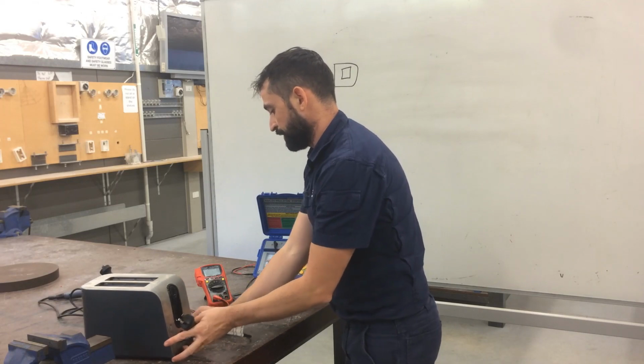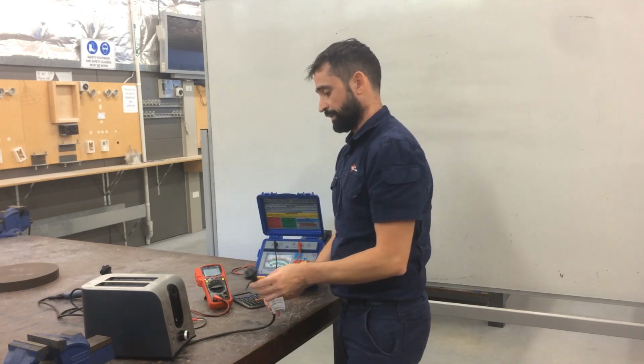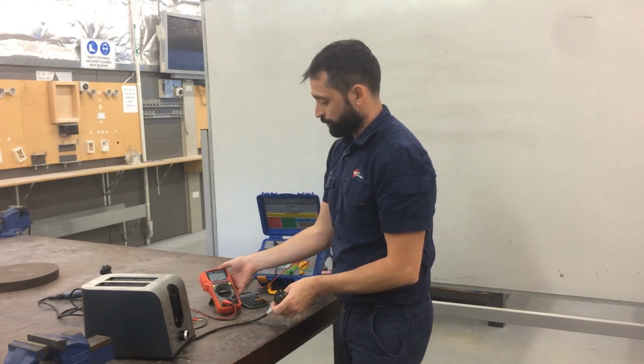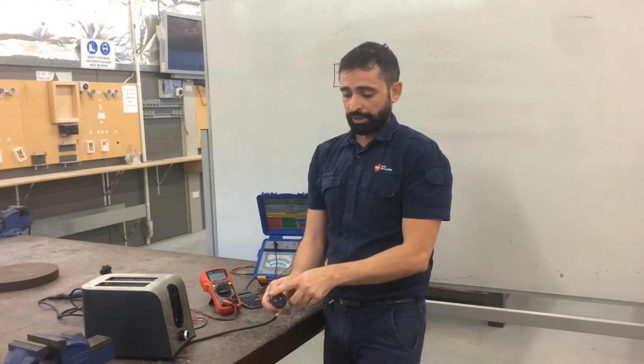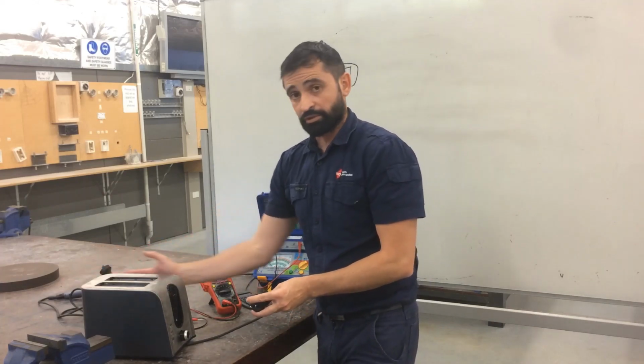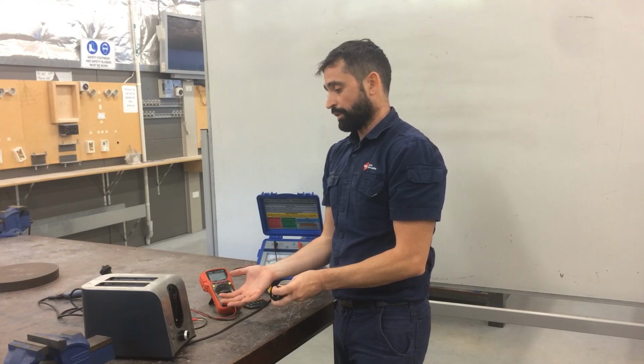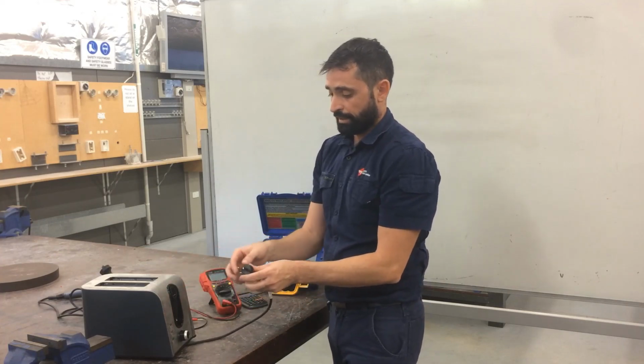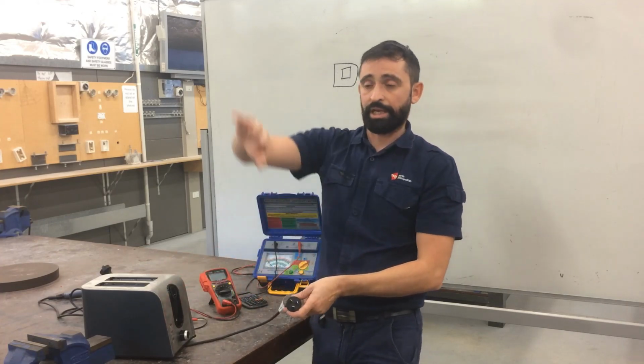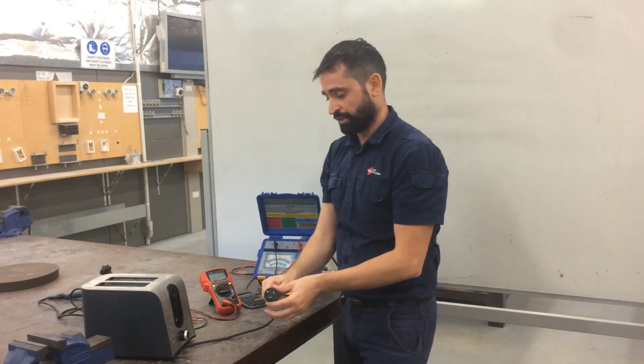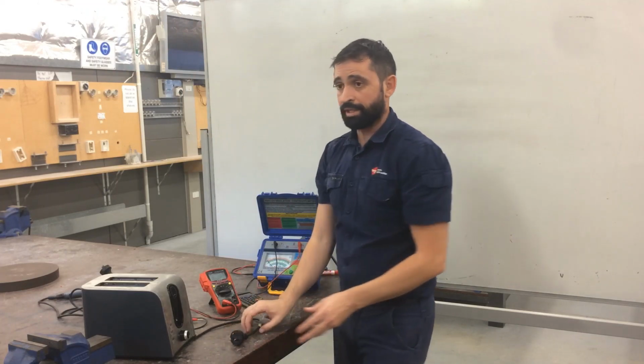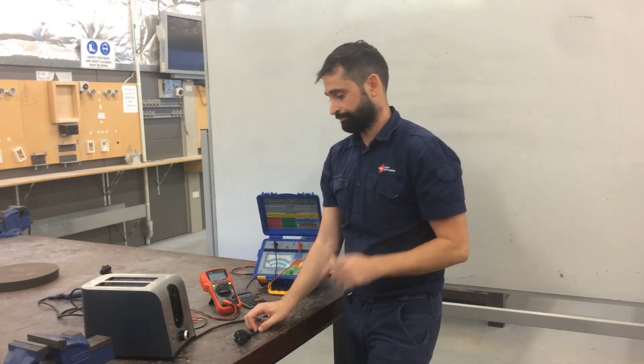And then what we're going to do is a resistance continuity test. So all we want to do is check our continuity between the earth pin and any exposed conductive part. So in the event of a fault, the fault current can go down through the earth cable, through the earth pin and into the earthing system with minimum resistance. Now the value that we allow is 1 ohm or less.